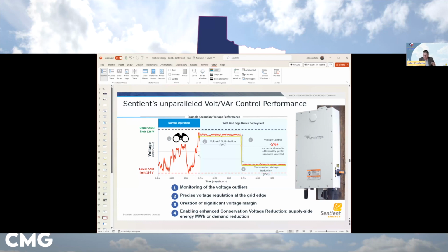Consequently, because we're able to control the voltage, on the primary side you can adjust the LTC - whether dynamic or set manually if you need to send a crew out - you can lower that voltage on the primary side. So with the implementation of grid edge control on the secondary side, typically we see about half of the overall energy savings and close to 40% of the peak savings, rather than just controlling on the primary side.